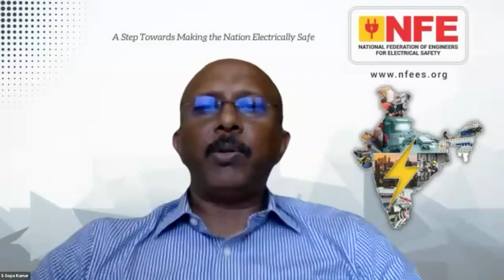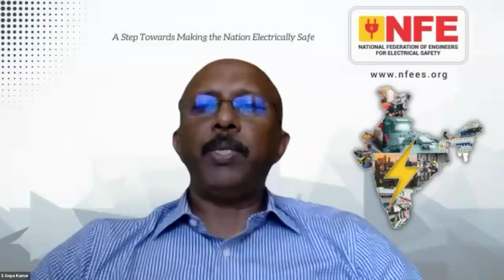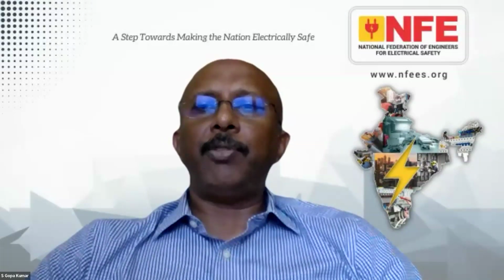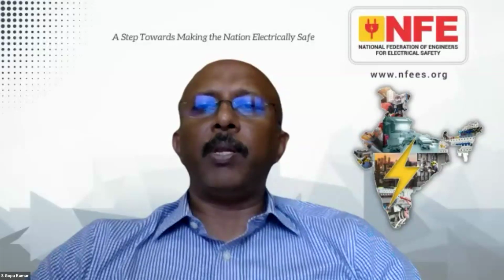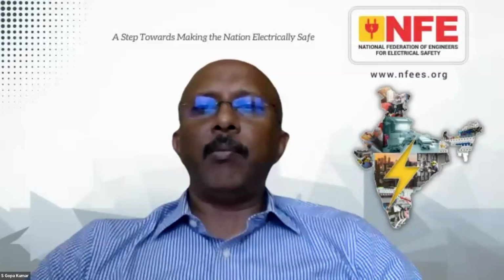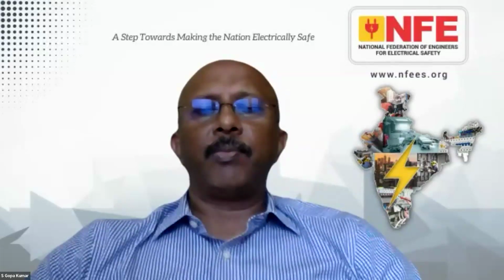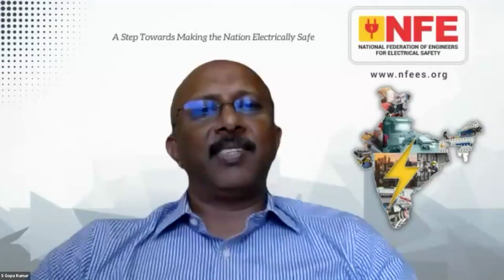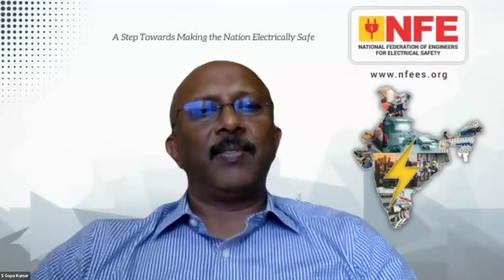The next question is from Mr. Ullas Vajre. Can loop impedance be measured in live circuits without shutting down the equipment in three-phase circuits like a motor? Yes, of course, a loop impedance test we have to do in a live condition only. So a loop impedance test and an RCD test, you have to do in a live condition. Yes, sir, you can add, sir.